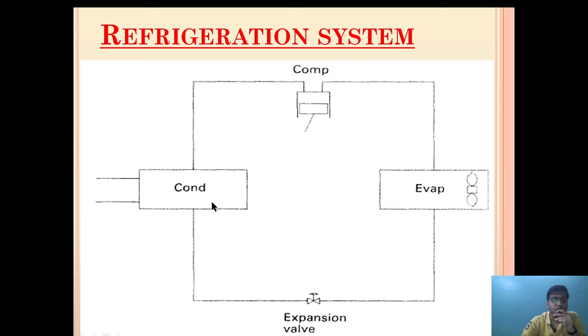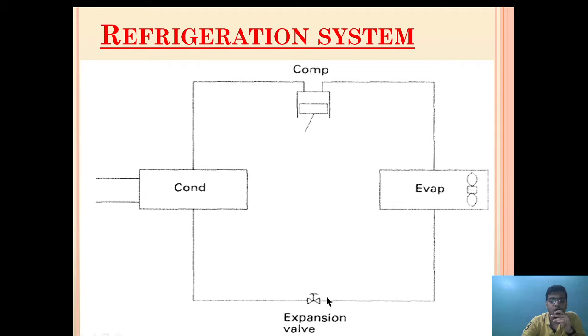The refrigerant is cooled down by the condenser, either by means of seawater or fresh water. As it gets cooled down, the gas form of refrigerant is changed into liquid form. That liquid form is then converted back into gas form through the help of the expansion valve. The expansion valve is a pressure controller which drops the pressure from high to low, and as it extracts the heat from the evaporator, it converts the refrigerant from liquid to gas.